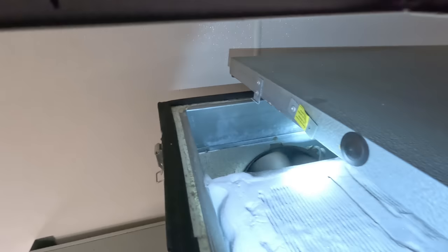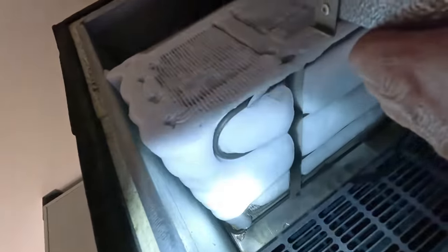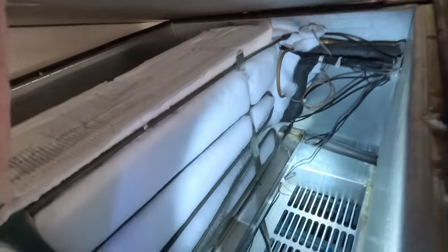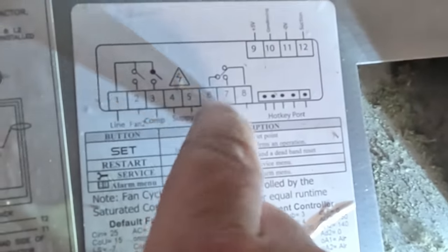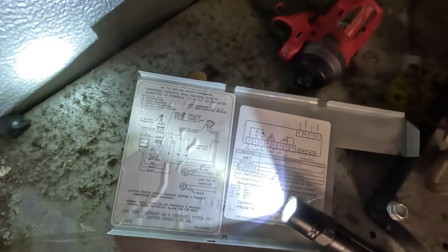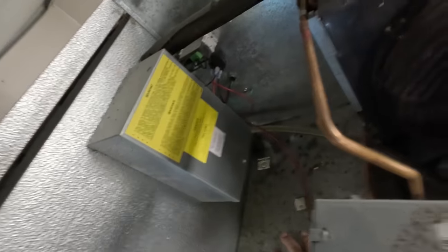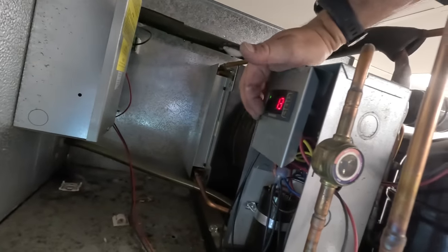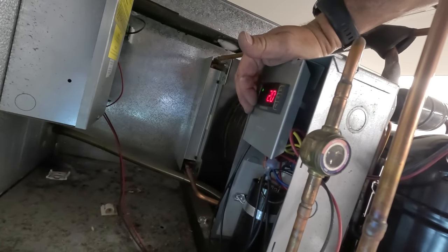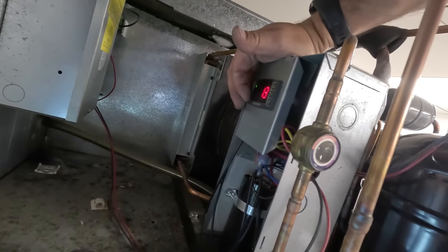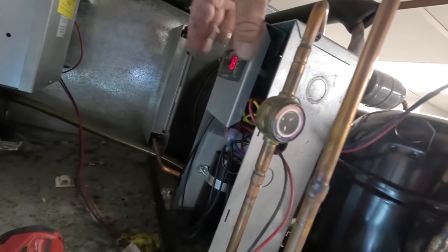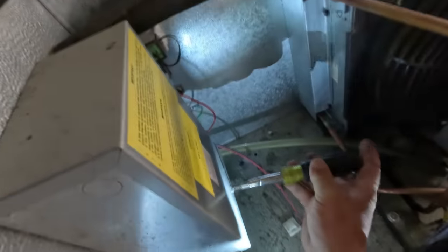Oh, look at that. I just bumped it and the fan's shut off. Makes you wonder, is that just a snap disk? Maybe it was making, not making. So we can see right here, the compressor and the fan are right here on this controller. It doesn't show a relay here on this. We've got two wires that come out of here. Come over to there, which goes into this box. This one might just control suction only. Let's see if this one has set points. CN, cut in, 20 psi, cut out, 7. So all this is here is a pressure control. This one doesn't do anything. So the other one's going to do all the work. Way fancier than I need to be.